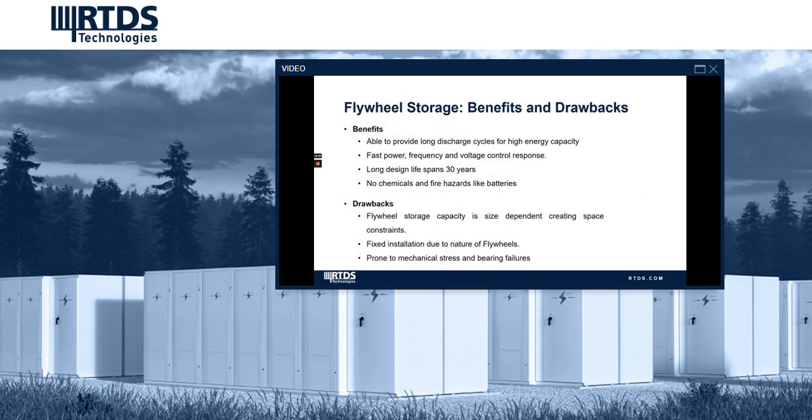Benefits of flywheels include the ability to provide long discharge cycles, long lifespans of 30 years, and they don't have fire and chemical hazards like batteries. The drawback is that flywheels are prone to mechanical stress and bearing failures. They require fixed installations and they are size dependent, creating space constraints.